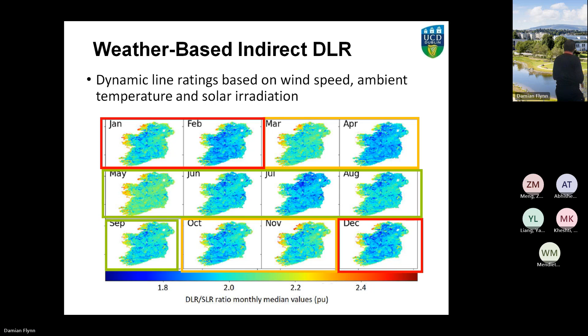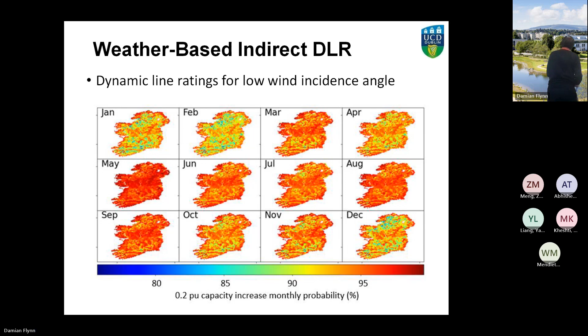Here we're looking at something similar: what is the likelihood that you could achieve a 20%, or 0.2 per unit, increase in your line rating? Again, you can see there's quite a seasonal variation, and perhaps a bit surprisingly, you're actually seeing the best advantage during the summertime. So it's not saying that you can increase your line ratings better in the summertime, but that the default assumptions are probably pretty good for the winter and maybe not quite so good for the summer. Or maybe it says something about the Irish weather, I'm not sure.